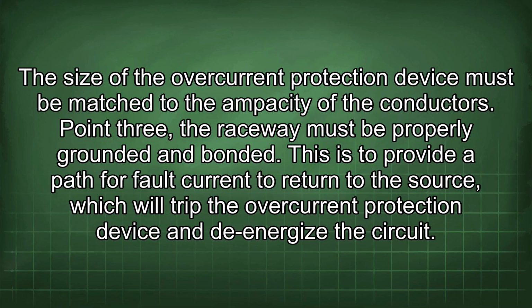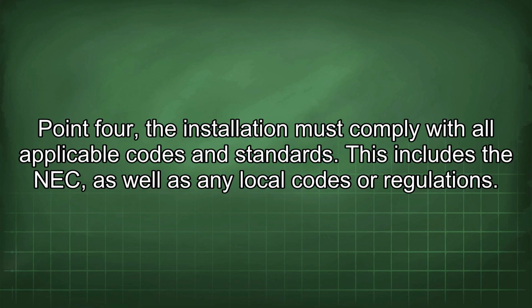Point 3. The raceway must be properly grounded and bonded. This is to provide a path for fault current to return to the source, which will trip the overcurrent protection device and de-energize the circuit. Point 4. The installation must comply with all applicable codes and standards. This includes the NEC, as well as any local codes or regulations.